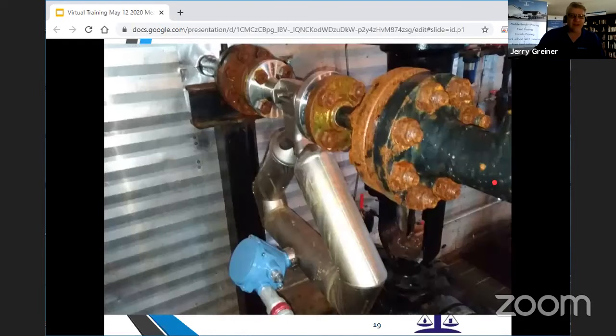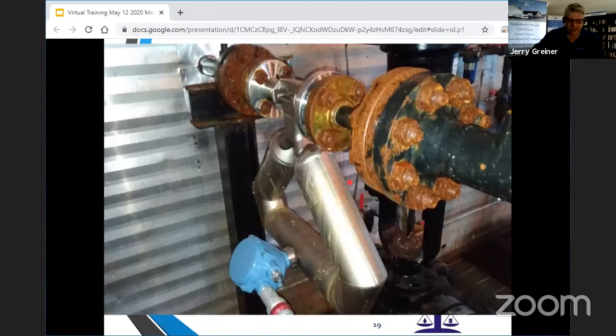This one passed verification. It's the triangular shape Coriolis, a 1 inch. On this, the problem was reported that the water cut was way out. So we thought the issue could be the sensor tube itself, something in the sensor tube. It could be in the core processor, which is in the little box attached to it, or else in the transmitter, or the FlowBoss 107, or the ROC that it goes to.